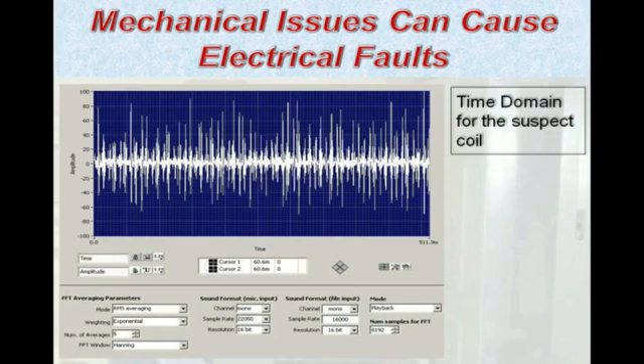On the time domain, one of the things we look for that's very typical with the instrument itself and this type of electrical component is, down the center of the axis, you have the broad band of white noise. And then we are on the lookout for deviations from that broad band, which would represent either electrical discharges or some type of mechanical vibration or looseness. In this illustration, the key thing that sticks out is we have deviations or excursions from that base broadband noise that are varying in amplitude across this half-second slice of the recording. So we have something changing in intensity that's either a discharge or some type of vibration.